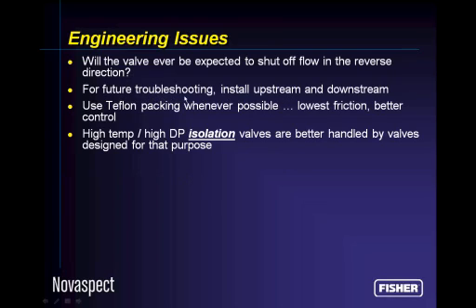If you're going to put a very expensive valve in the line, it would be a good idea to install an upstream and a downstream pressure gauge so that we could use those pressure readings, the P1 and the P2, for troubleshooting at a later date. Use Teflon packing whenever you can. It's the lowest friction available. Friction is a control valve's enemy. You get the best control valve, and what I mean by that is you get the best production cost, the highest profits, the lowest variability if you use a low friction valve. So use Teflon packing whenever possible.